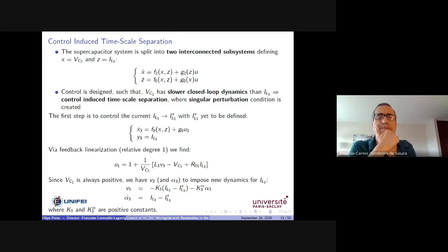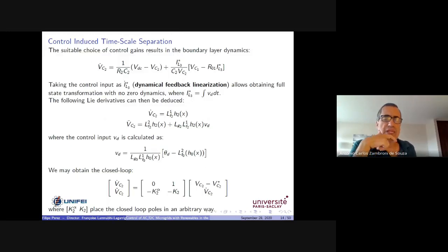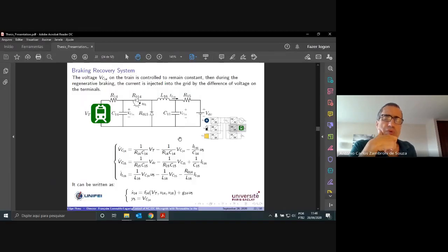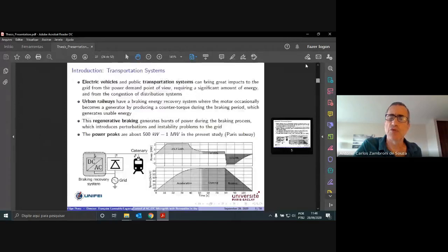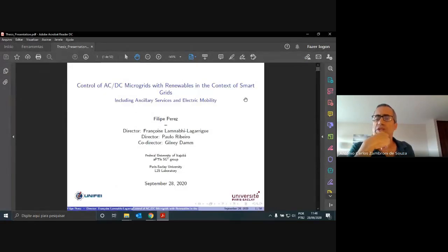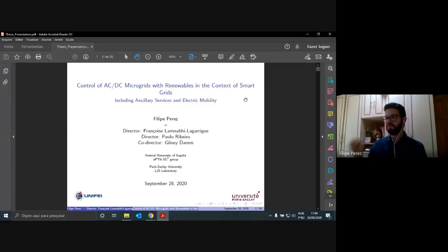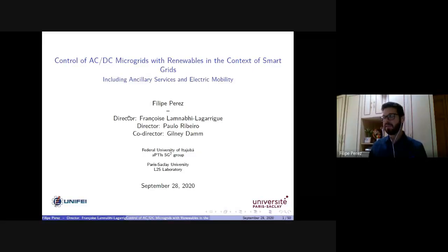I do have a question on page 22. When you say that each battery system has a maximum capacity of 3.6 kilowatts and operates in droop control mode, is it correct? The battery is in droop control mode, or you are talking about the converter mode? Because in general, we say that to dispatchable units, right? Yes. I mean the converter. And we are dealing with a storage unit, so you can apply the control scheme for the converter of the storage unit.